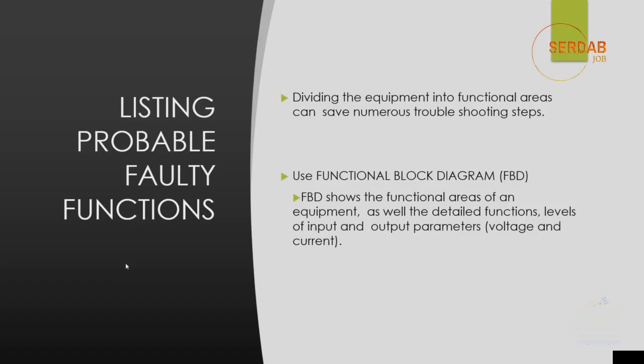Now, you need to list probable faulty functions. You need to divide the equipment into functional areas in order to save troubleshooting steps. Use functional block diagrams, or FBD, to show the functional areas of the equipment, as well as the detailed functions, levels of inputs and outputs, and parameters for voltage and current. Making that diagram will save you a lot of time. Make sure to state the input and expected output for each block, then start measuring.